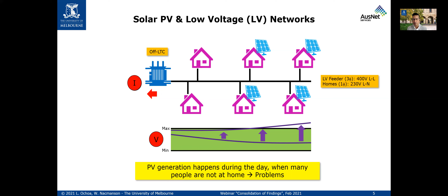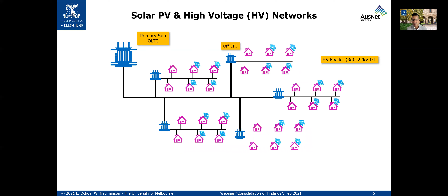In terms of voltages, you will have an effect called voltage rise that can even go beyond the statutory limits. So when people are not home and photovoltaic generation happens, we might have problems, not all the time, of course. And this is not just in the low voltage networks, this is as well in our high voltage networks, 22 kV, 11 kV, or 33 kV networks.